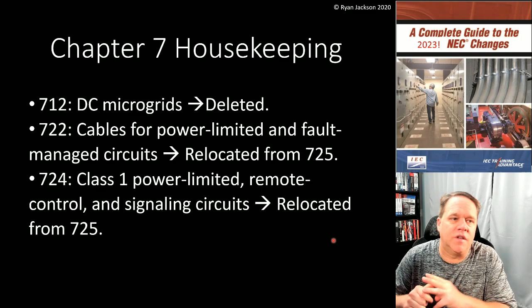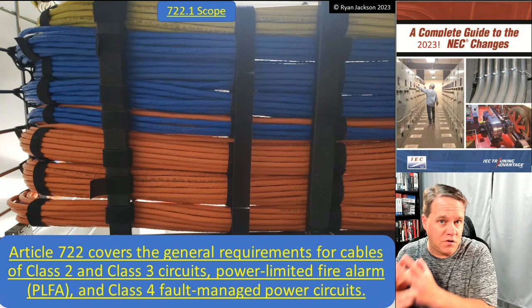If you're familiar with Article 800, this is similar to Article 800. So it's one article that just, you know what it does? It removes repetition from the code. Article 725 used to say, hey, these are all the cable types, and these are the properties they have to have, and these are the listing requirements, and this is how you secure and support them. And then Article 760 said the exact same thing for low voltage power limited fire alarm. Why do we need to keep on repeating these things in the code? Let's make a general requirement and give it a new Article 722, and that's what they did. So 722 is new, and it results in Article 725 being smaller and easier to work with. Same with 760.